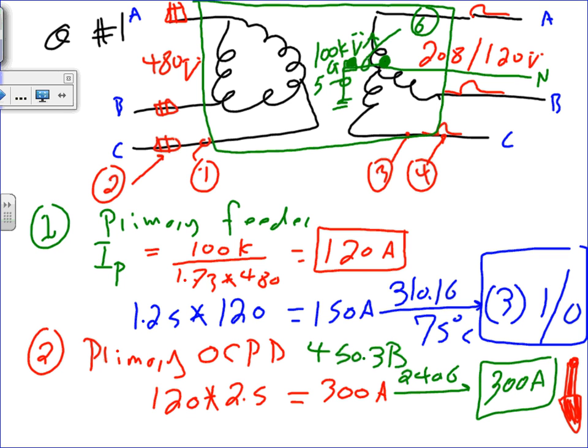We'll get into that one, guys, deeper when we go to transformers and generators especially. But for transformers, always ask yourself: if you created a new neutral, it's a separately derived system. If it was a delta-delta, not a separately derived system. If it's a Y-Y and you tie the two neutrals together, which we rarely, if ever, use, non-separately derived system. 99% of the time, you're going to see a transformer delta, Y, create a new neutral.